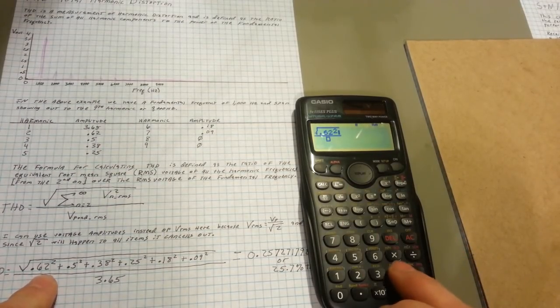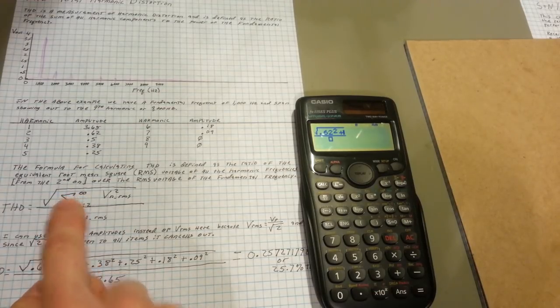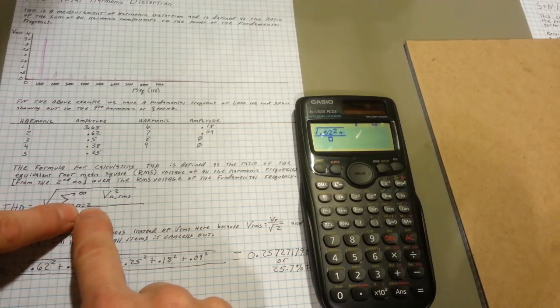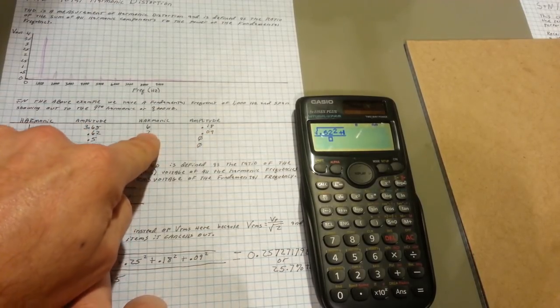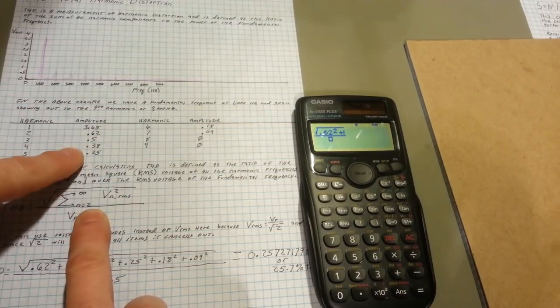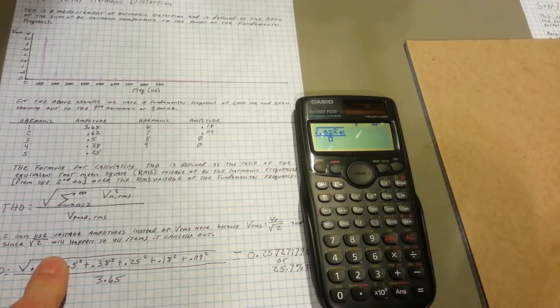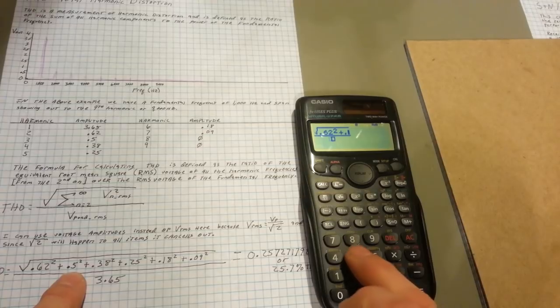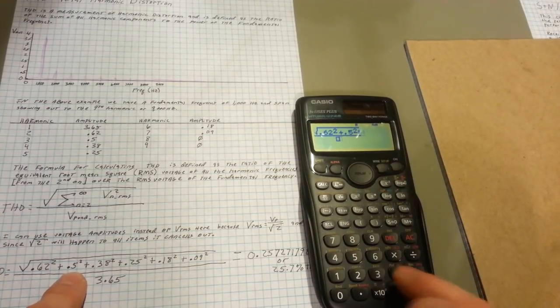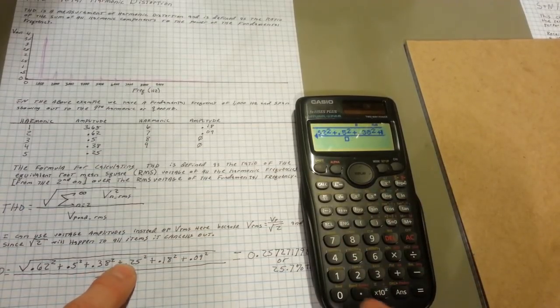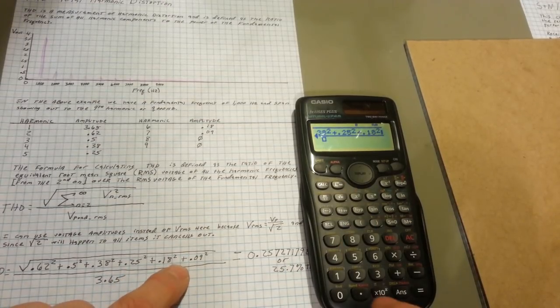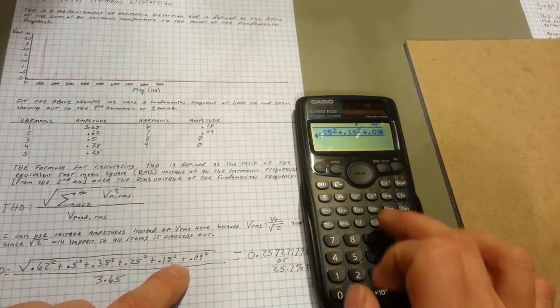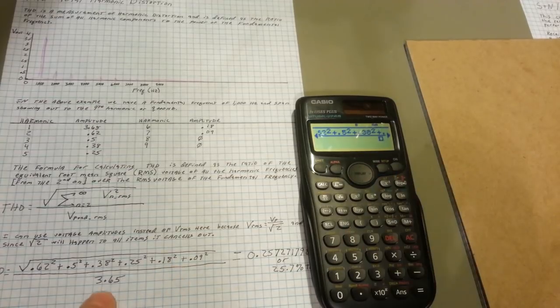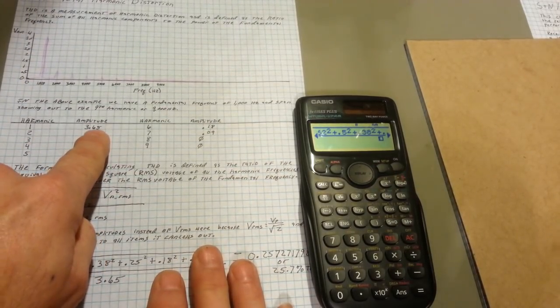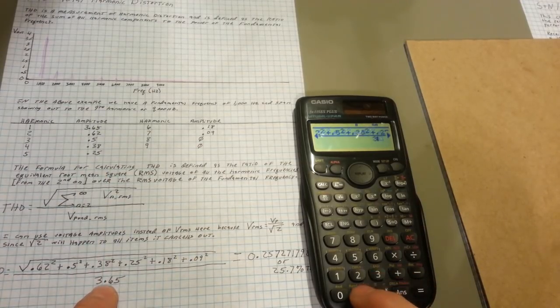0.62 squared plus. Now, you've got to remember, I said this is a summation, meaning everything between the second harmonic and infinity. We only have measurable to the 7th harmonic. So the sum of all of those measurements, from the second harmonic to the 7th. So 0.62 squared plus 0.5 squared plus 0.38 squared plus 0.25 squared plus 0.18 squared plus 0.09 squared, and then at the bottom of our fraction we're going to have the measurement taken at the fundamental frequency, which was 3.65.